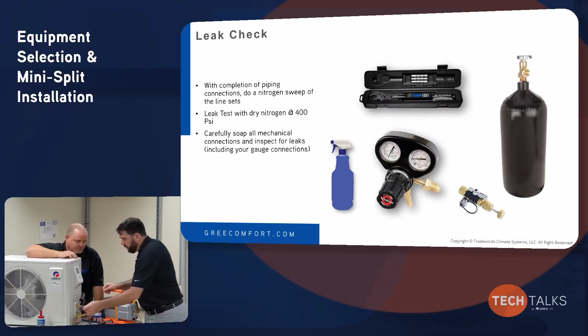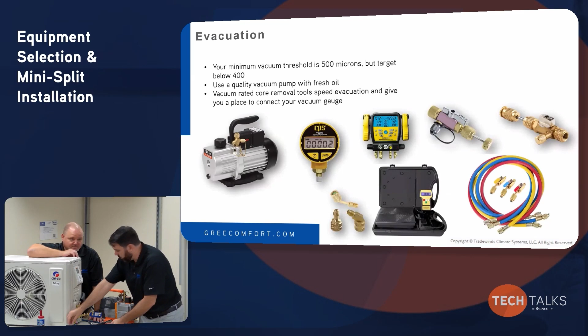So let's move forward a little bit, and just before we do, I'm not sure if we need to make mention of this. Your flare nuts that come from the factory on the outdoor unit have these little copper bonnets as a cover to keep trash out. I have actually had pictures of these being left on and forced up into the line set. So make sure when you're putting that factory flare nut on the pipe that you get this bonnet out of the way. I save these too, because if I ever need to cap something off, I'll grab one of these and put it on there so it's a good clean cap. I have a little bag of those that I save.